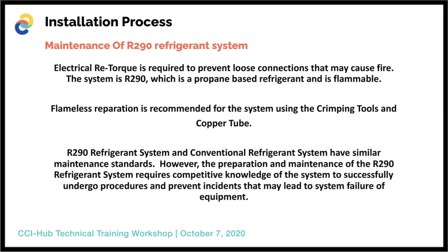Electrical re-torque is required to prevent loose connections that may cause fire. The system is R290, which is a propane-based refrigerant, and it's flammable. Flameless reparation is recommended for the system using crimping tools and copper tube. We already bought crimping tools intended for this repair, for a previous problem and for future problems at these stores. So the clients are confident that the repair uses only crimping tools and no oxyacetylene in the repair of the R290 refrigerant system.